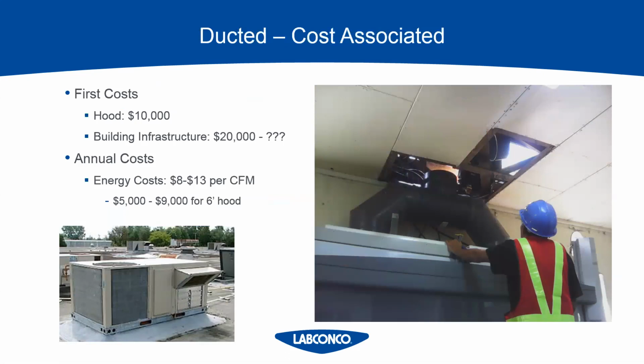And then if you put sophisticated controls on it, then it would be upwards of $100,000. So this number is extremely variable, and it would be on a case-by-case basis. Because some buildings, think about it, if you're doing a retrofit or you're replacing your fume hood, and you already have the duct run installed, you can save a lot of that money. So that's on the other side of the coin.